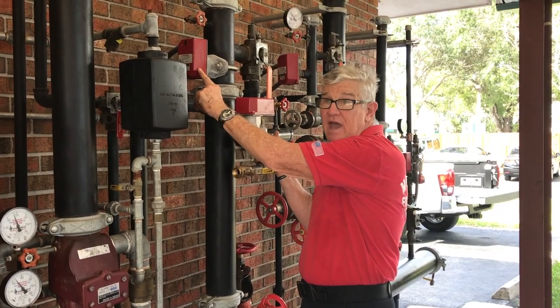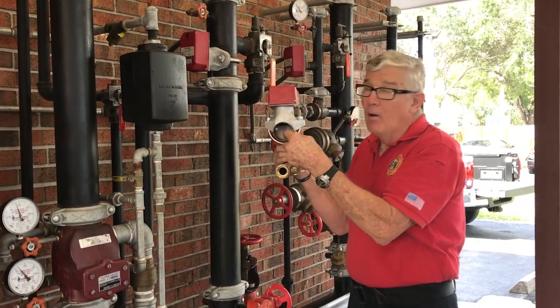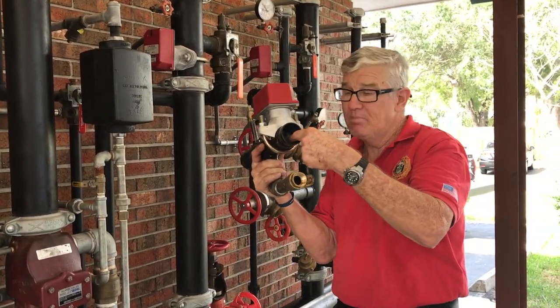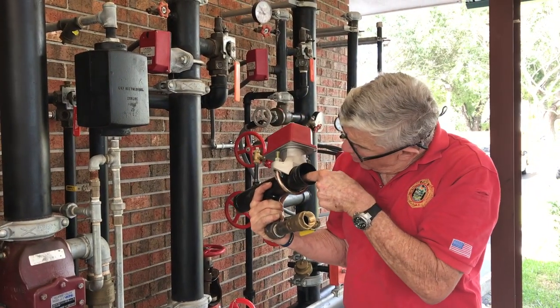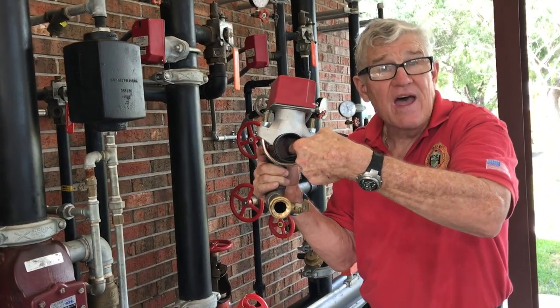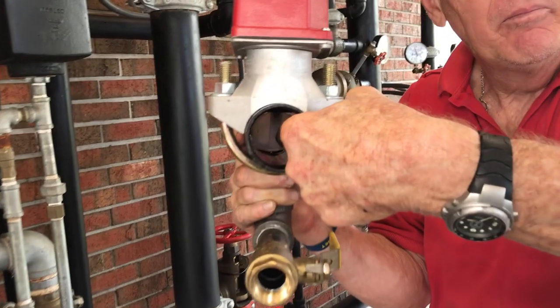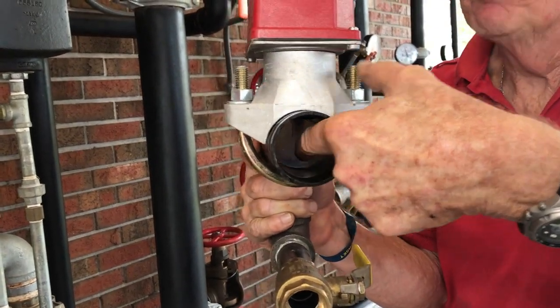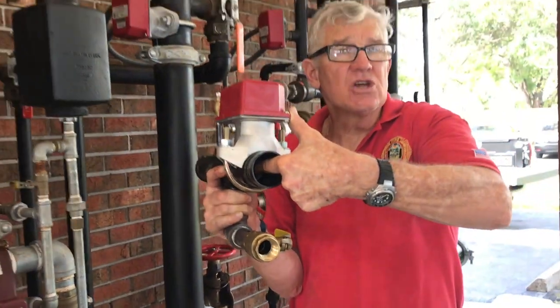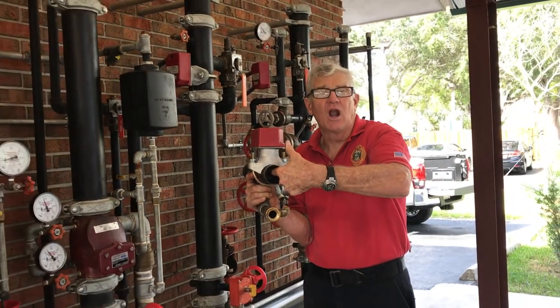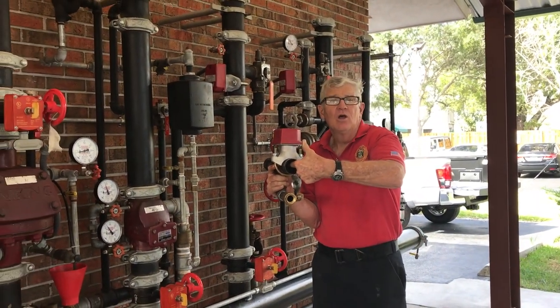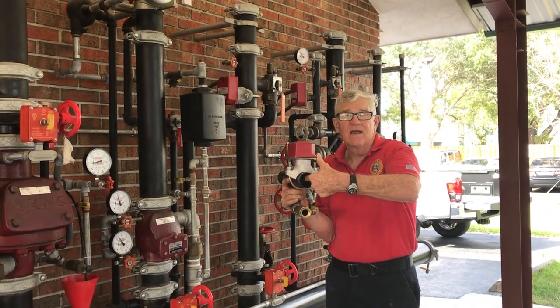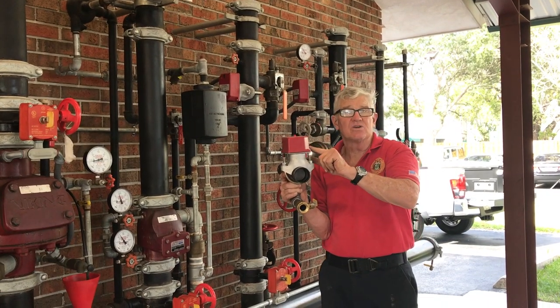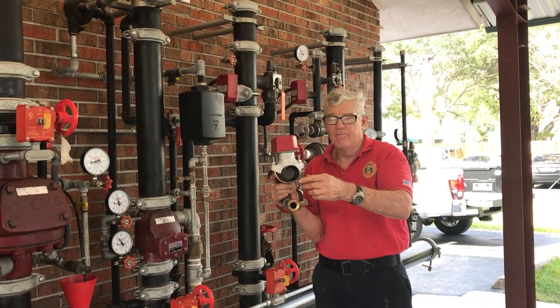Water flow indicator bolted to the pipe. The flow of water moves that flapper, which completes a circuit and initiates a water flow alarm within 90 seconds. And it can be adjusted, the delay can be adjusted inside here.